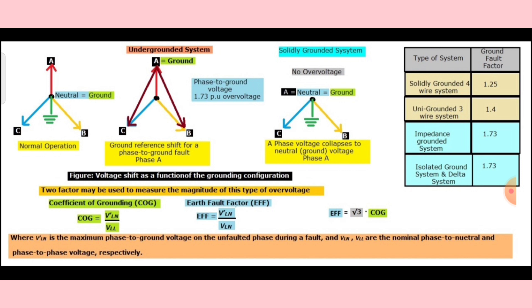On the other hand, earth fault factor is basically the ratio of VLN (the maximum voltage of the unfaulted phase during single phase to ground fault) to the rated phase to neutral voltage of that system. In other words, it is the square root of 3 times the coefficient of grounding.